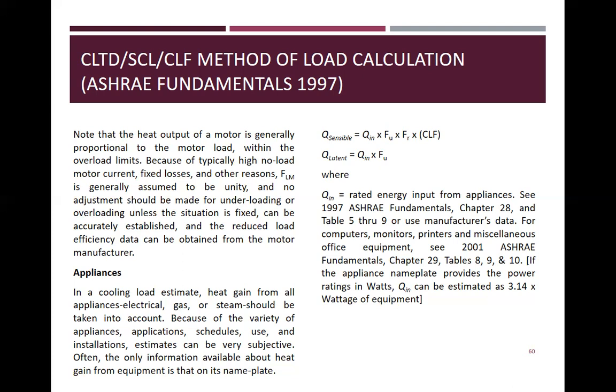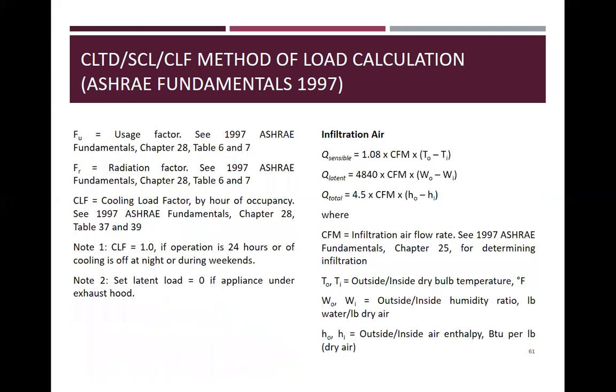Okay. Fu is the usage factor. See 1997 ASHRAE Fundamentals, chapter 28, tables 6 and 7. Fr is the radiation factor. See 1997 ASHRAE Fundamentals, chapter 28, tables 6 and 7. Then CLF is the cooling load factor by hours of occupancy. See 1997 ASHRAE Fundamentals, chapter 28, tables 37 and 39. Note 1: CLF is 1.0 if operation is 24 hours or cooling is off at night or during weekend. Note 2: set latent load equal to 0 if the appliance is under an exhaust hood.